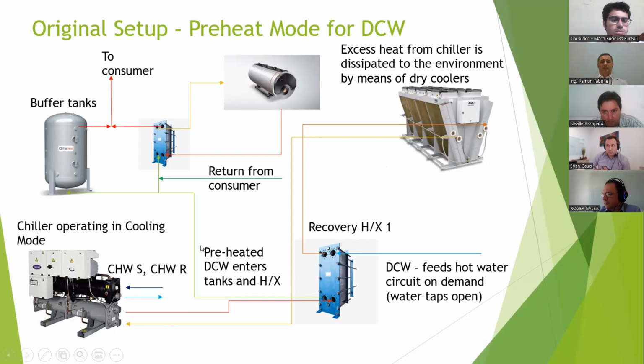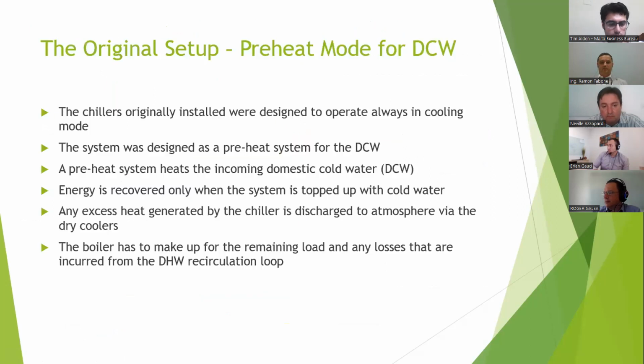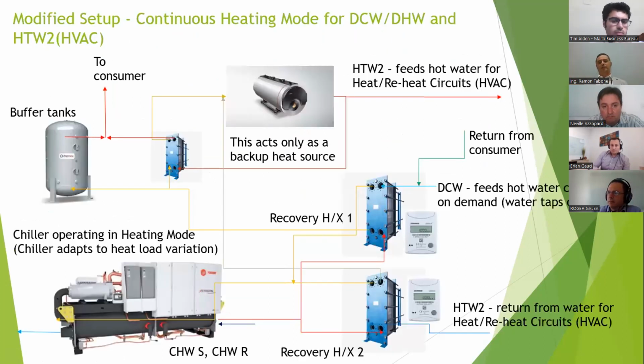So, as I said before, the old system dissipated heat to the atmosphere at some times. Still, from that 50 degrees and beyond, we had the boilers to heat the water up to the required temperature. This system, because of the low temperature, was not integrated with the HVAC, for obvious reasons. So this is basically the description that I gave here. So what changed? What was the optimization? Basically, there was a change in design.